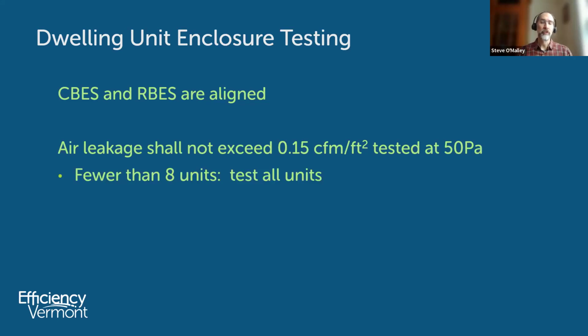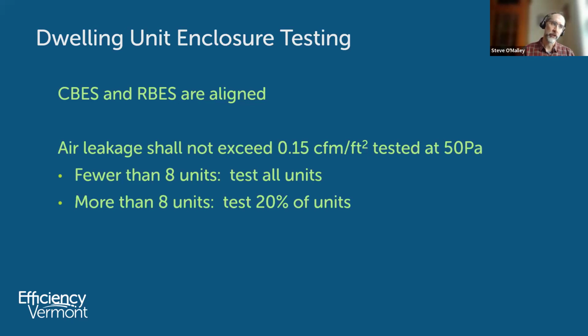Testing requirements have changed as well. In the 2020 CBES, it was something like 10% of units tested, and it didn't really talk about building size. Now, if you have a small building with fewer than 8 units, you need to test all the units. If you have more than 8 units, you test 20% of the units, and within that 20% it has to be a smattering: a top corner, a bottom corner, a middle unit, a middle floor unit, etc.